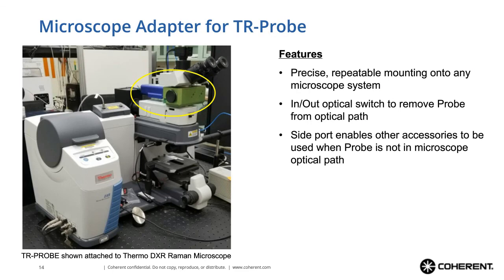The TR Probe can be mounted to a microscope with a microscope adapter — here shown mounted onto a Thermo DXR Raman microscope. The microscope adapter is permanently connected to the microscope, allowing you to easily connect and remove the probe head as desired. An integrated optical switch allows you to remove the optics from the microscope beam path and engage a side port that connects to other accessories when the probe is not in the microscope optical path, making it very versatile and advantageous to operate.